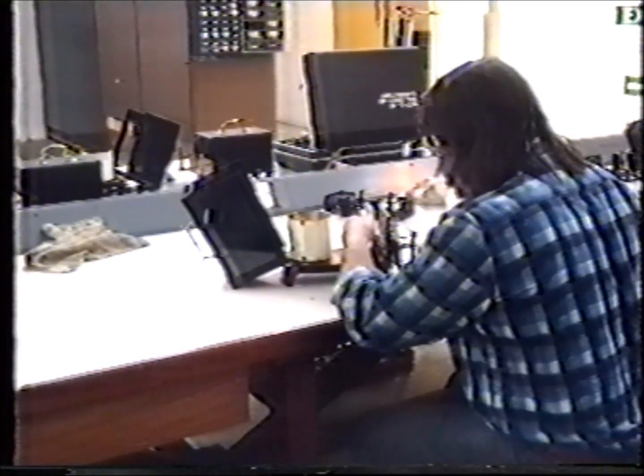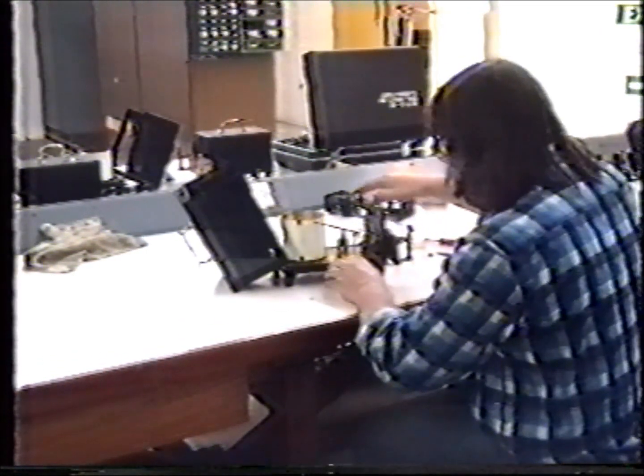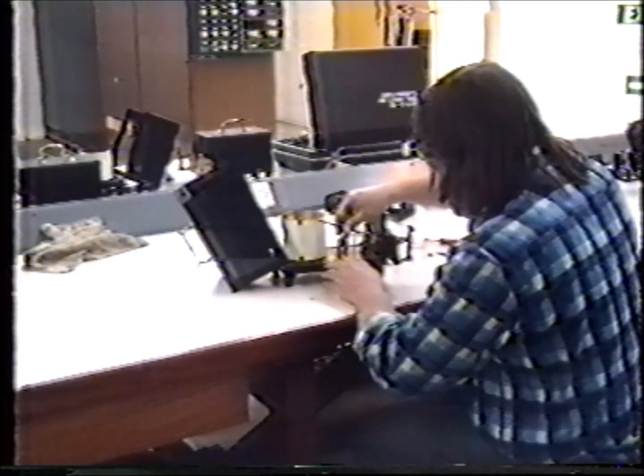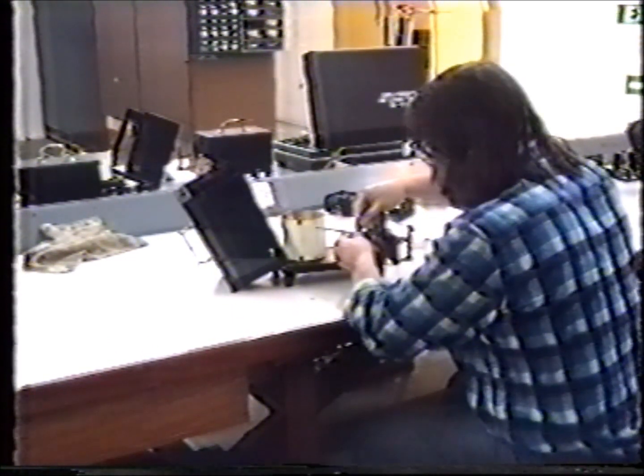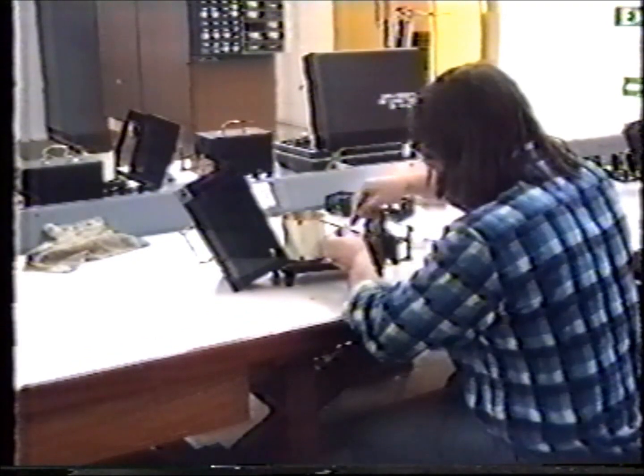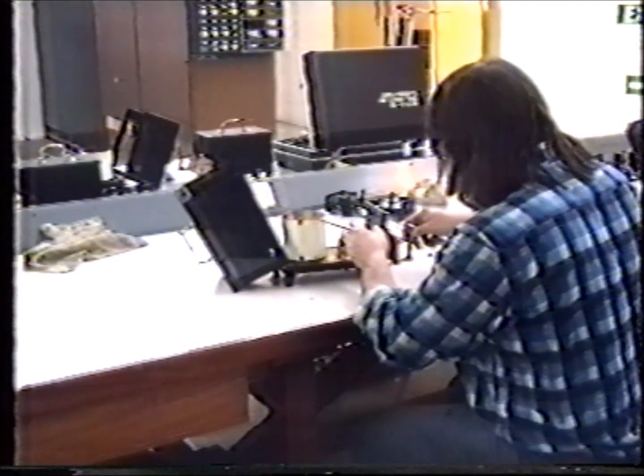This is sad, as a great deal of care and attention is paid to its setting up and calibration in the laboratory. Of course, it must be remembered that after a period of storage and transportation to an outstation, the hair may have altered its characteristics, and so a simple setting up procedure should be undertaken on arrival.